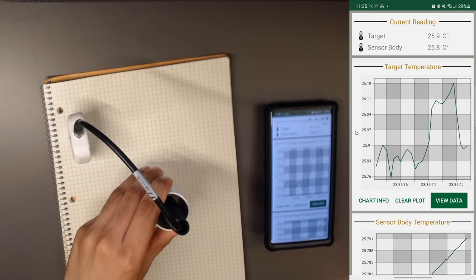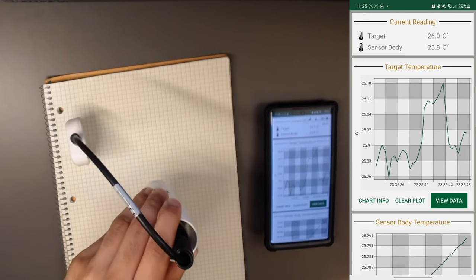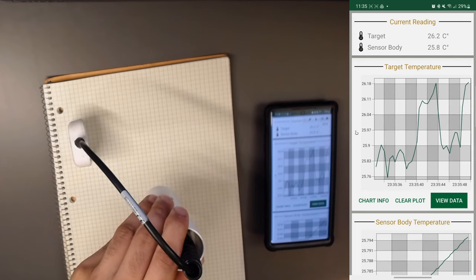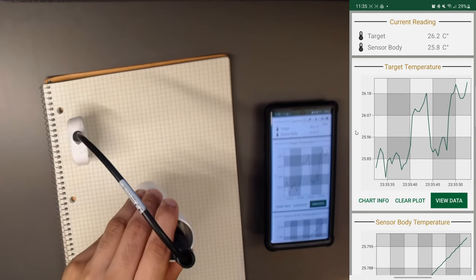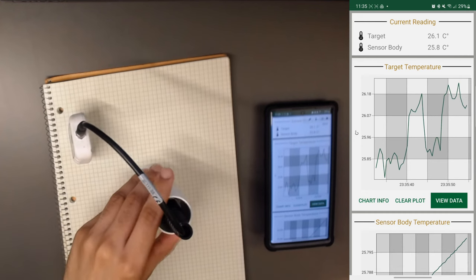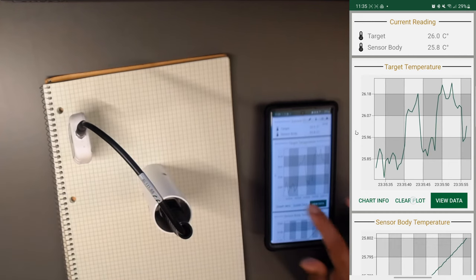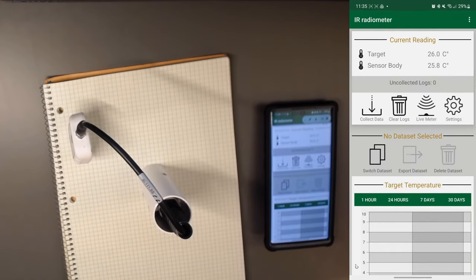When I take a measurement a few centimeters higher, I get another higher reading, since the sensor is actually measuring the reflected radiation in addition to the emitted radiation from the notebook. For this reason, take all your measurements with the IR radiometer right up against the surface to block out the background radiation.